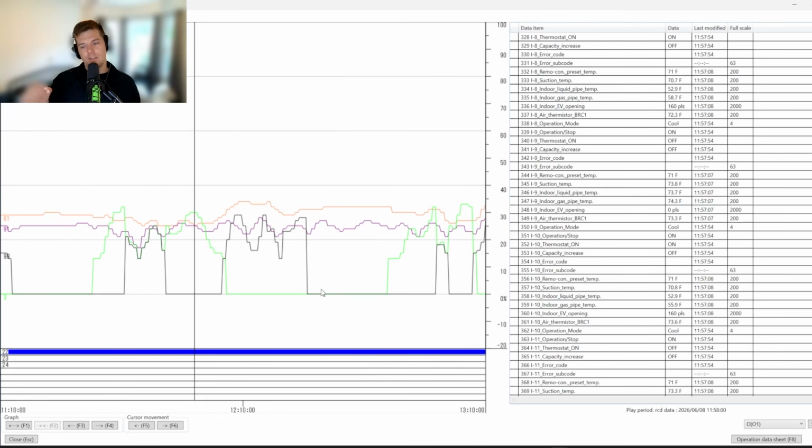Maybe there's bigger things that we're not seeing on a system like this that can cause compressor failures, can cause oil return. When you look at a system like this and you see these squiggly wiggly lines where the saturation temperature and the suction temperature are modulating like that, where the saturation temperature set point is also modulating and the compressors don't settle out in normal operational windows, then you have to look at this and say, okay, how many times does this happen a day? Because if this happens 9 times a day, is that enough to kill a compressor? It is over 2 years. It is over 3 years. It is over 5 years. Those things play a bigger factor in a lot of this stuff.